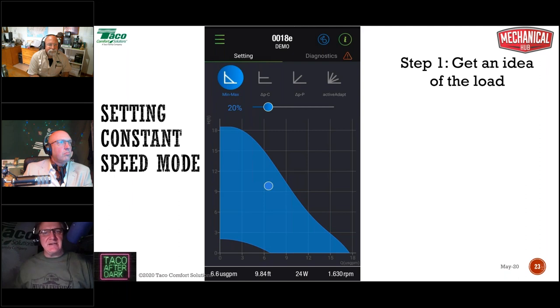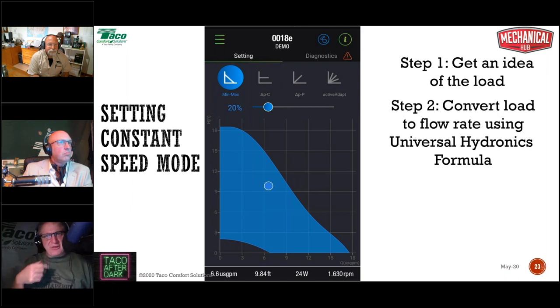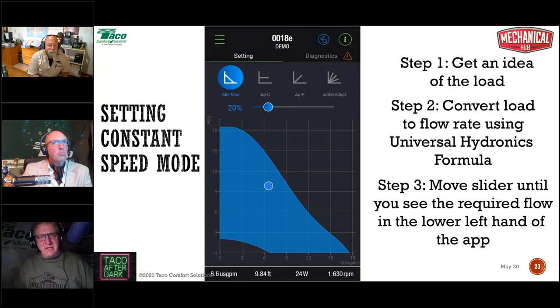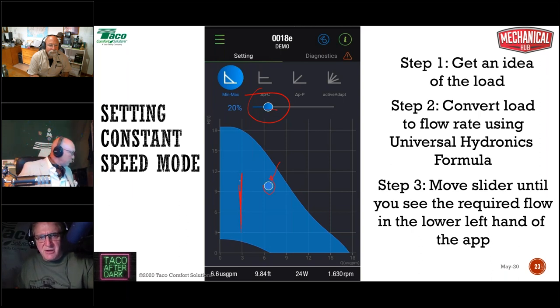So you get an idea of the load, and then you convert that load to flow rate, 30,000 BTUs, using the universal hydronics formula, GPM equals BTUH divided by delta T times 500. And then you simply move this slider until this dot moves to where you want it to be. So let's say we needed 3 gallons a minute. You adjust this slider until this dot lines up on 3 gallons a minute. That's where it's going to line up.